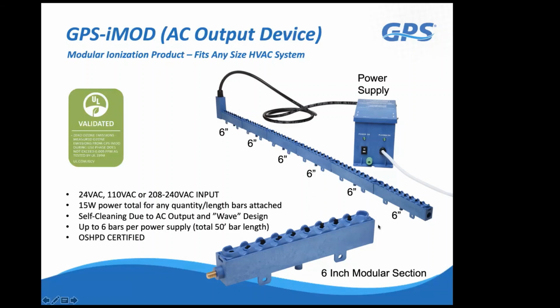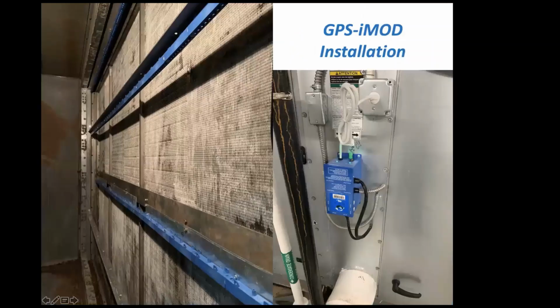Because this is alternating current, or AC output, unlike the other devices with the wiper blade, they do stay clean. From a maintenance standpoint, we recommend that once per year, when you're changing the filters, you take a rag with some rubbing alcohol and walk down the bar and wipe these brushes off if you see any debris. Some people will use a toothbrush just to knock off any debris that builds up, or you could use a paintbrush. Just don't use an actual wire brush on the system. You could also use a shop vac with a brush attachment. That also works well, so it's very easy to clean. It's a fiberglass constructed device, so you could take a blowtorch to it. It'll just glow orange, but it doesn't catch on fire or smoke. It's very non-conductive because it's fiberglass, and it's non-corrosive, so even in a pool environment, that's not going to impact it.